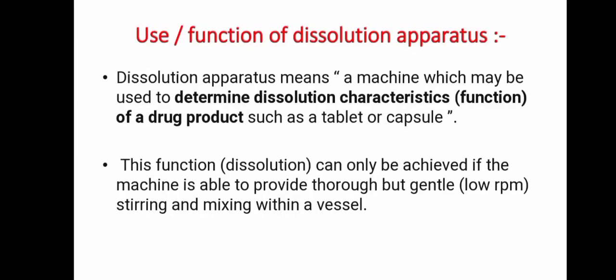Function of dissolution apparatus. A dissolution apparatus is a machine which may be used to determine the dissolution characteristics of a drug product such as a tablet or capsule. This function can only be achieved if the machine is able to provide thorough but gentle, low RPM stirring and mixing within a vessel.